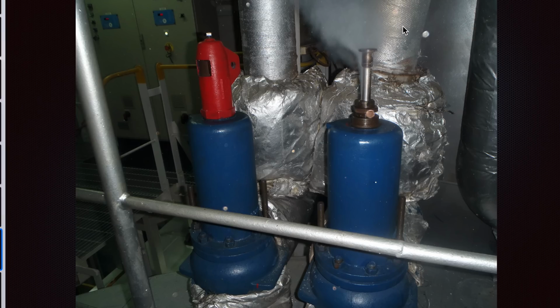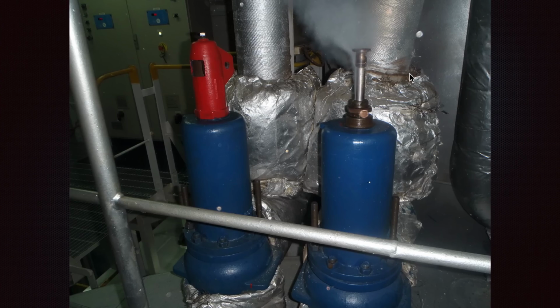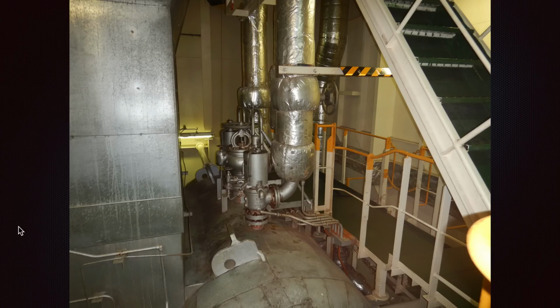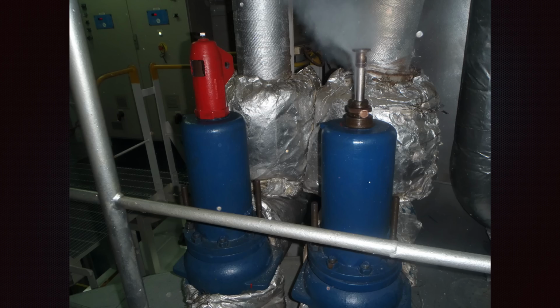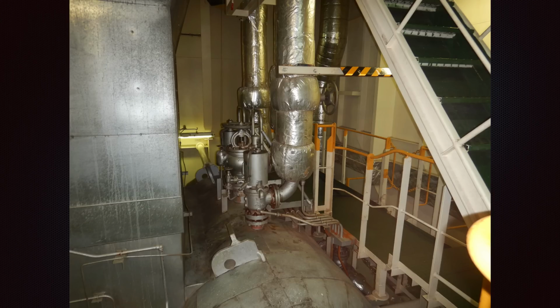And this is how a vessel must properly be designed, driving all that steam and heat far away. If we compare, this is the Aalborg and Hyundai built, and this is a Mitsubishi built ship where all the steam goes out to the engine room, as I have seen.